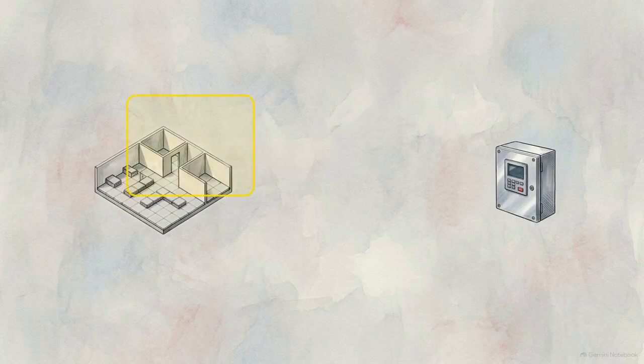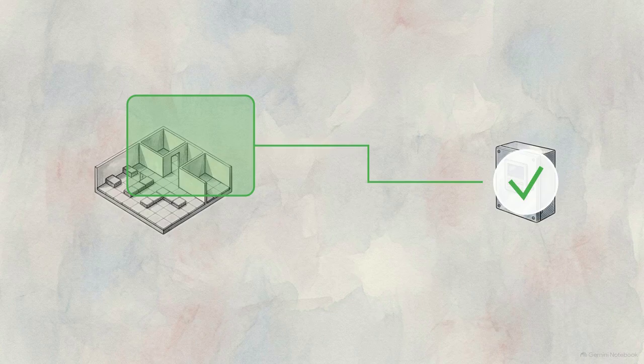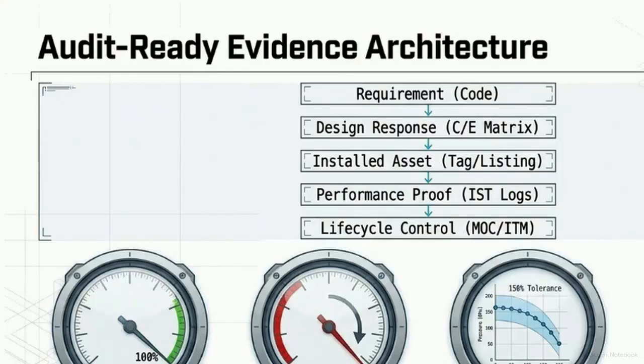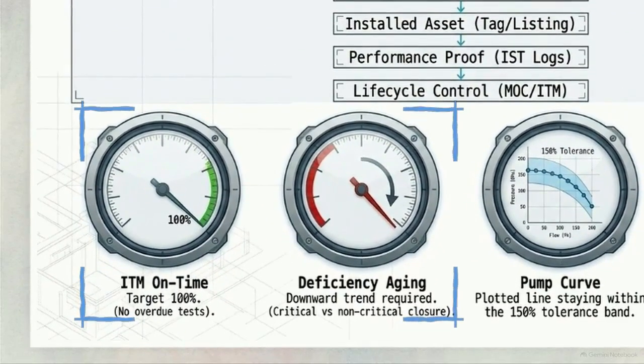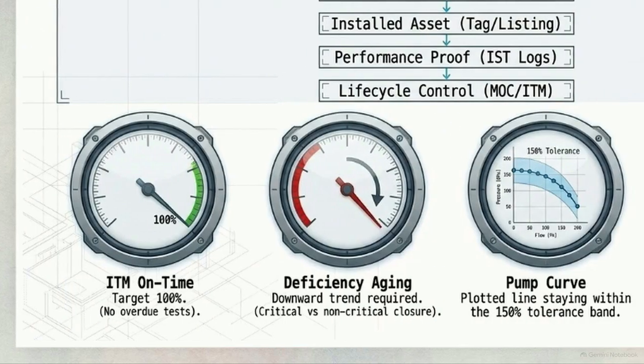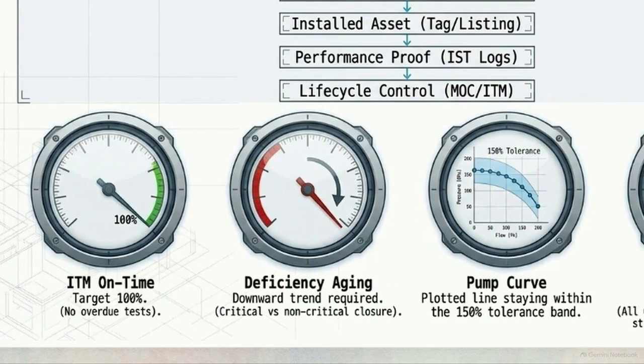Prohibited practices include undocumented software disables, unapproved isolations at the panel, and leaving physical valves closed without tags. Managing these risks requires a named risk assessment, active temporary fire watches, and an end-to-end alarm confirmation upon restoration. Evidence retention functions as a critical component of the physical protection system, tracked through specific metrics like ITM on time and deficiency aging. Missing or falsified testing records are an operational defect, hiding silent configuration risks until it's too late.